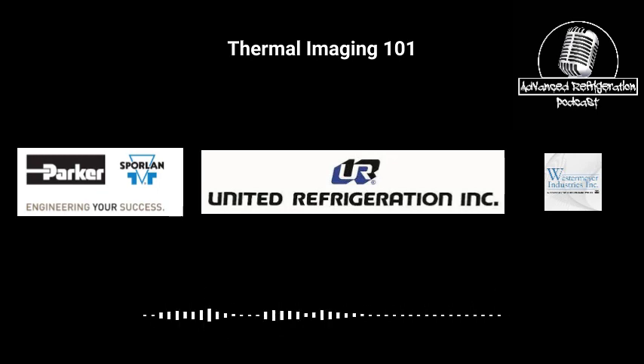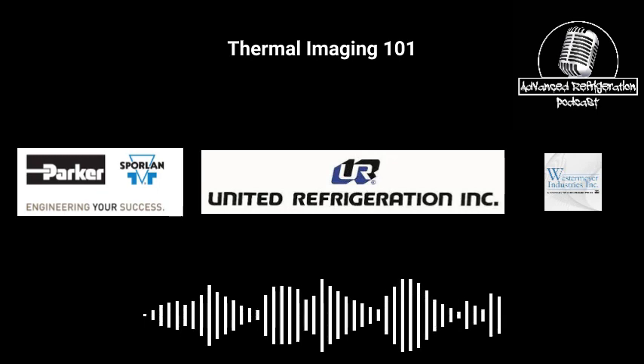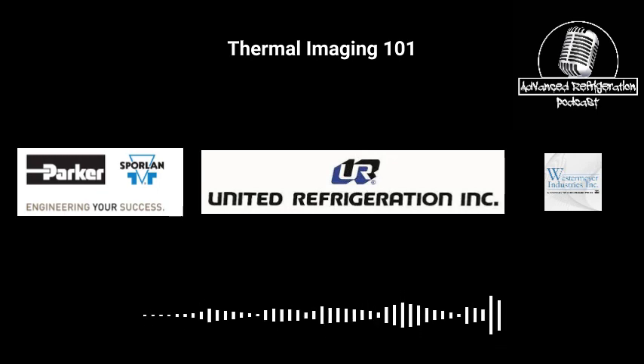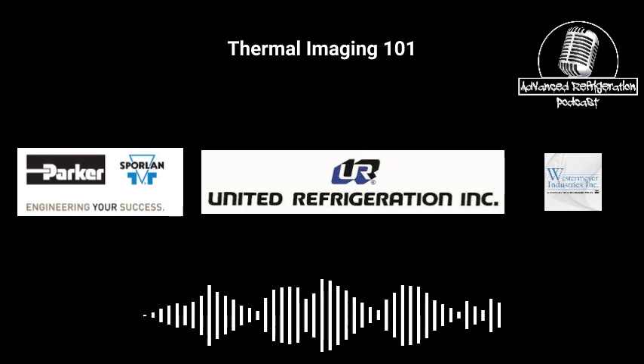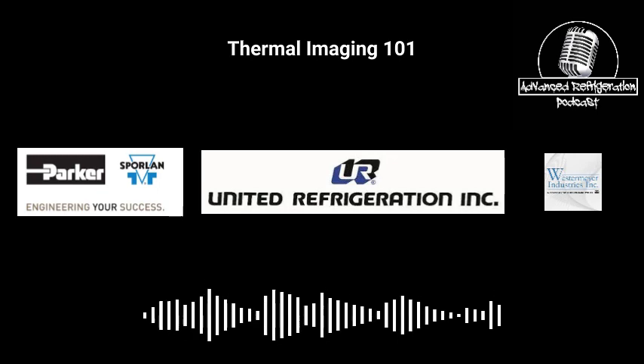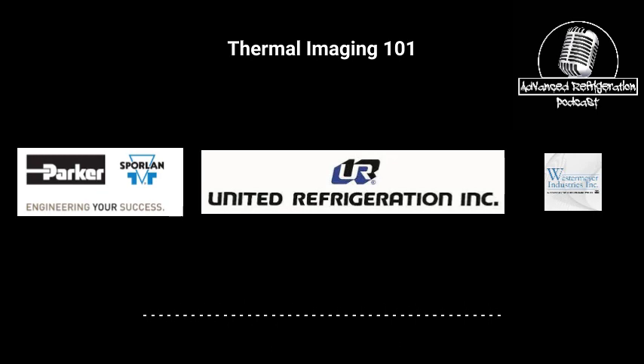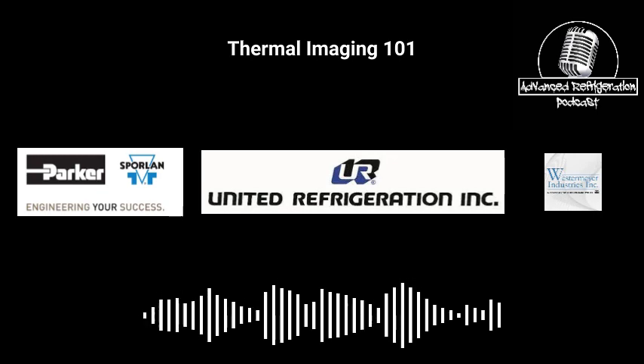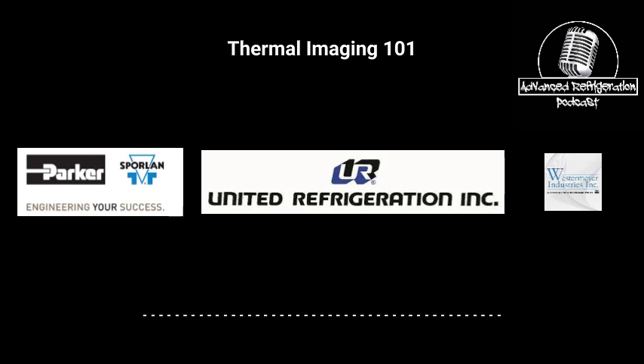Now, what could you use thermal imaging for? For us in the HVAC and refrigeration trade, a ton: checking compressors, checking door gaskets, checking door frame heaters, checking heaters on coils, checking for air gaps and air leaks. So we're going to go over each one and break it down.